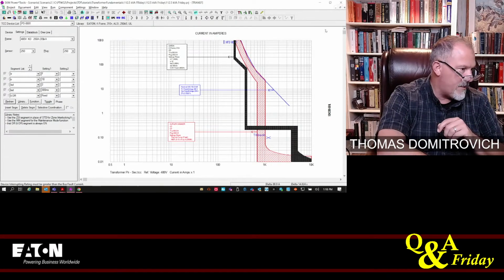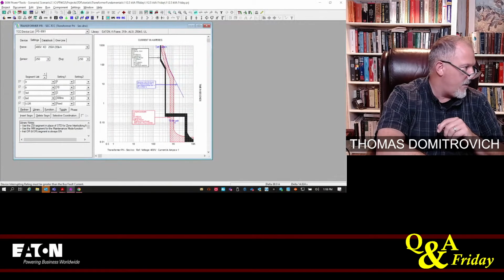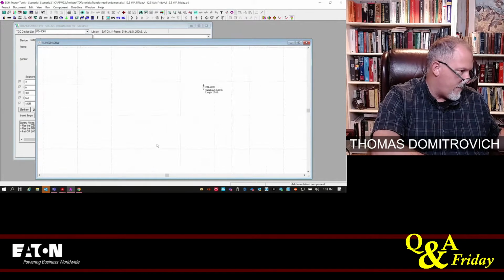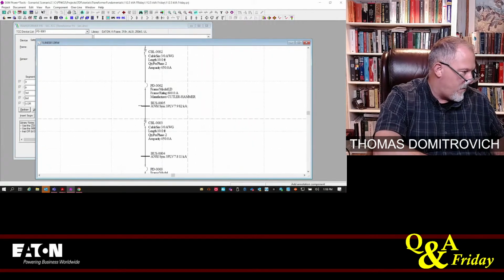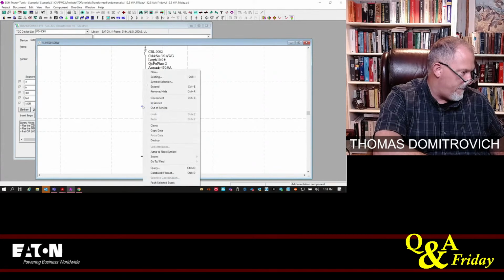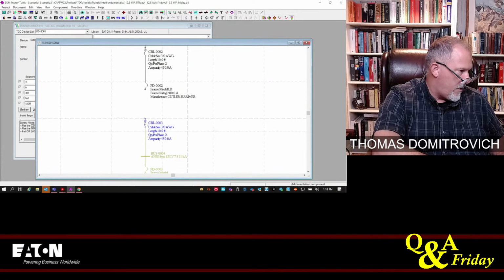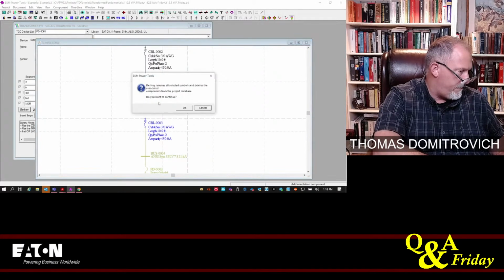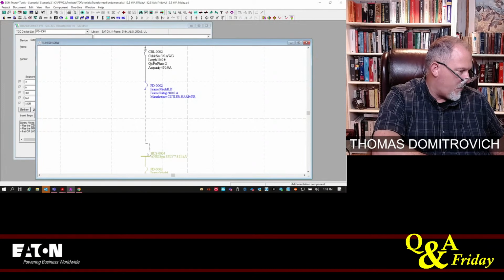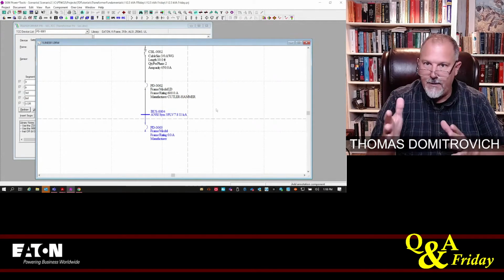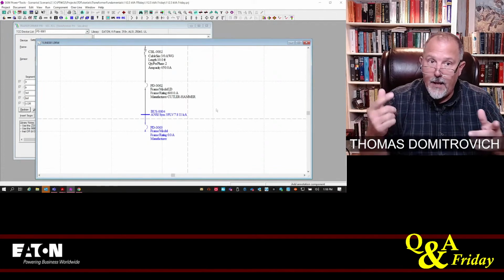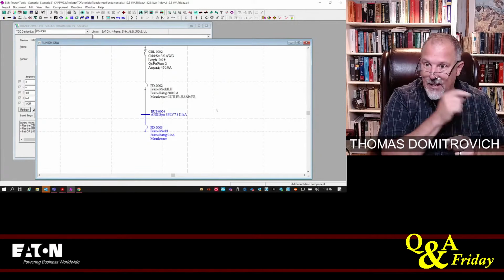you know what else I'm going to do? Go to the one line. Here's what we're going to do. We're going to blow this away. Destroy it. We're going to connect this breaker. Yep, we're going to connect that breaker. So we just basically got rid of that secondary disconnect, and we put the money in an electronic trip unit upstream.